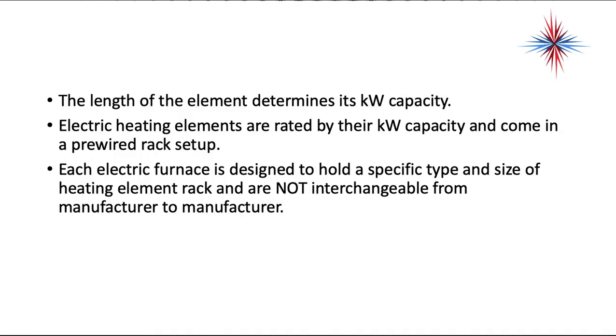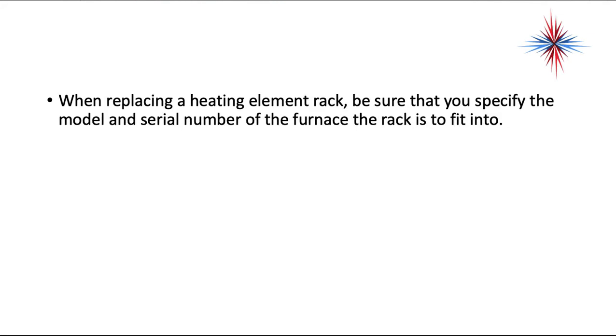The length of the element determines its kW capacity. Electric heating elements are rated by their kW capacity and come in a pre-wired rack setup. Each electric furnace is designed to hold a specific type and size of heating element rack, and they are not interchangeable. When replacing a heating element rack, be sure that you specify the model and serial number of the furnace the rack is fit into.